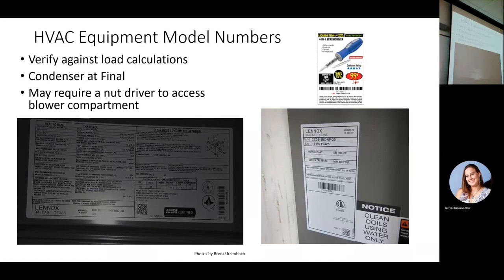So just a couple other things that we're going to jump through. Some of this is for inspectors and some of it is for you contractors, but you submit a plan, you do a load calculation, you identify what equipment you're supposed to put in there. So we have a complete set of plans, but then you get out there and do an inspection and you don't know what size the furnace is. And you can't read this label very well. I need to change the contrast on that. But if you're inspecting against the load calculation, you probably ought to verify that it's the right equipment.